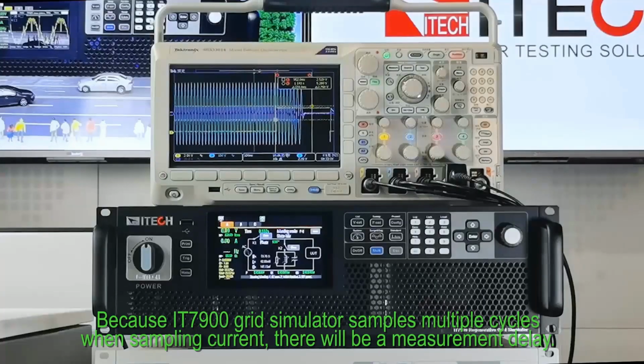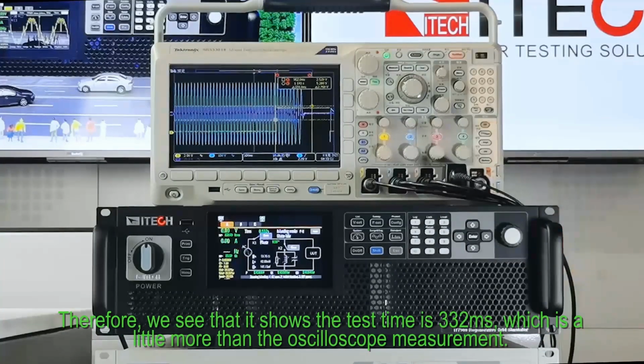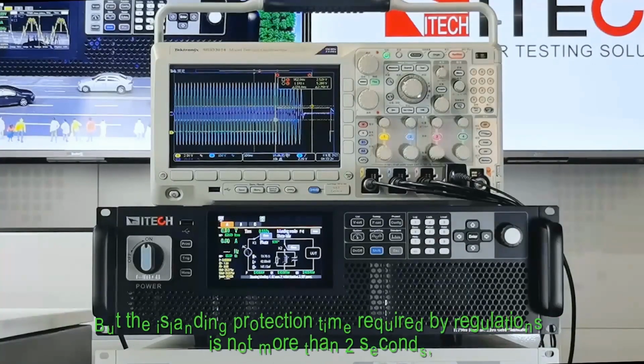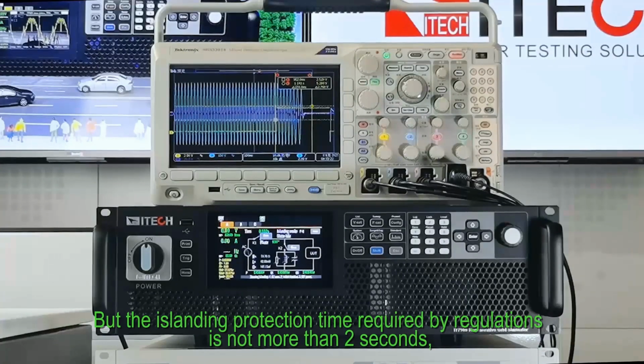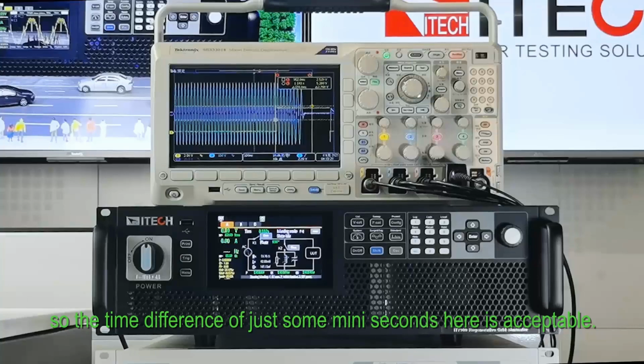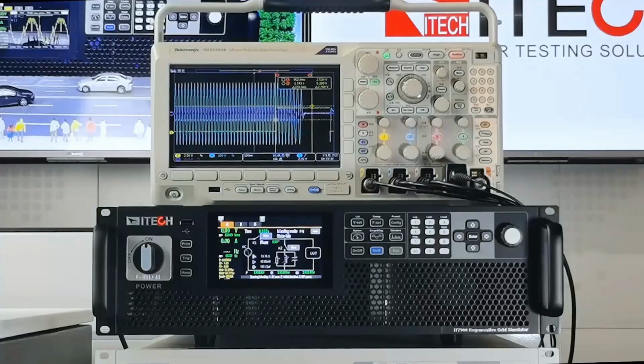Because the IT7900 grid simulator samples multiple cycles when sampling current, there will be a measurement delay. Therefore, we see that it shows the test time is 332 ms, which is a little more than the oscilloscope measurement. But the islanding protection time required by regulations is not more than 2 seconds, so the time difference of just some milliseconds here is acceptable. That's all for today's demonstration.